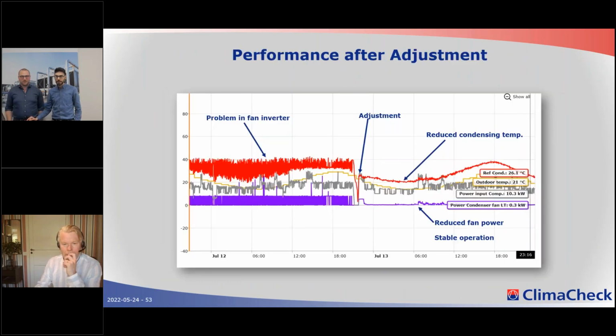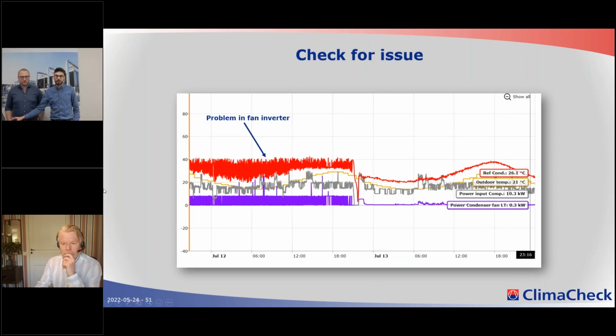Now, in that particular example that I showed, we're also measuring the fan power, and the fan power usually is around 0.3 kilowatts. And here, we see the fan power is around 8-9 kilowatts. So we've got a huge amount of energy going to the fans, and this is not really normal. Also, the system itself is unstable. Here, after adjusting it, you see how stable the condensing temperature is, which is directly affected by the fans.